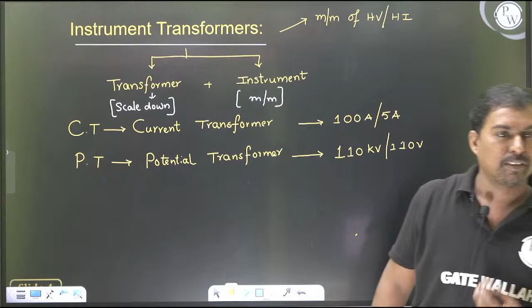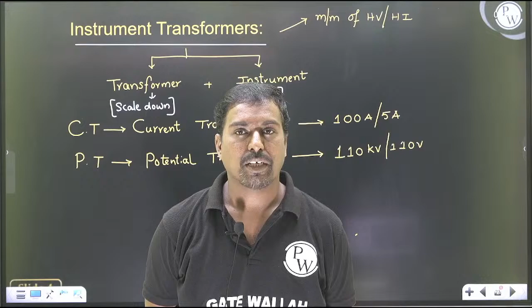See, whenever you want to measure the high voltage or high current, even though PMMC we have range extension, and moving iron also we have range extension, but we cannot use them directly for high current measurement and high voltage measurement. That's why instrument transformers we are using for the measurement of high voltage and high current. So they are suitable for measurement of high voltage, that means in the range of kilovolts, and high currents.